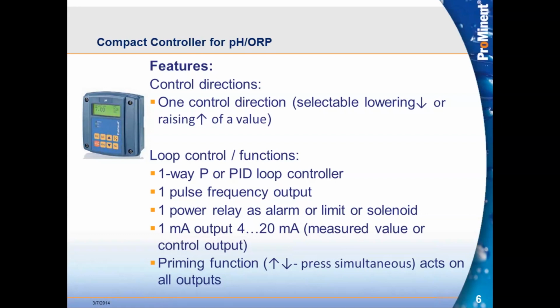Where the D1C, really you could feed both chemicals simultaneously. It's not done very often. It's more common to feed in one direction only, so that's not really taking anything away. The only time we tend to see that really is in pH controls. Sometimes we're trying to stay in a deadband, and you'll see caustics being fed on the low end, and then acids being fed on the high end to stay in that loop. But it's kind of the exception more than the rule.